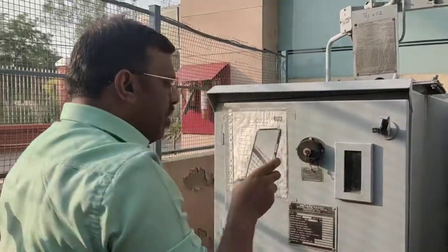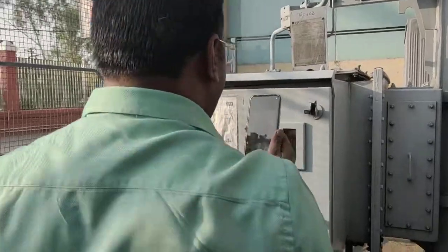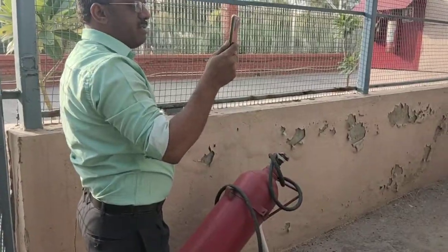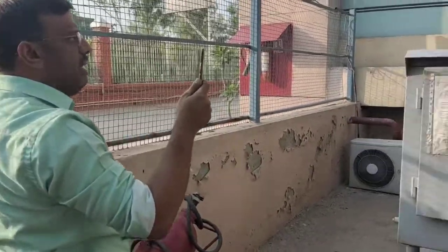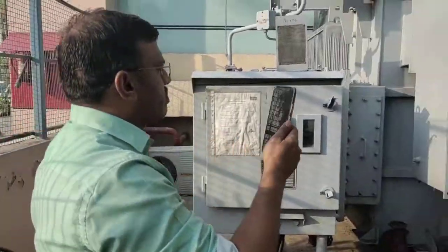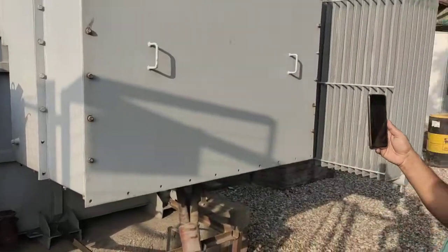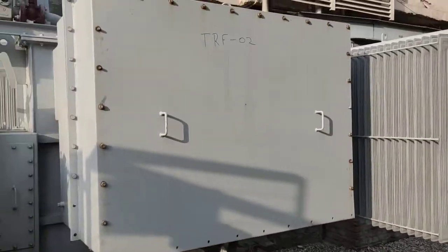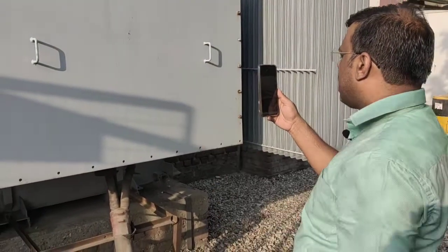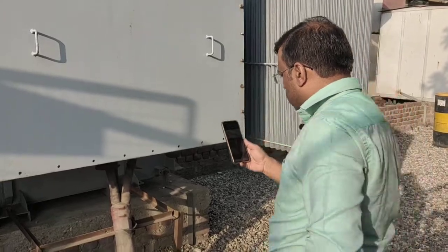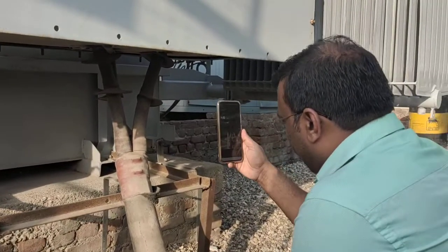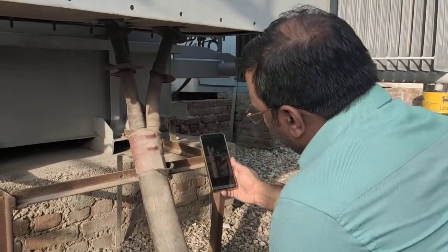Okay, so now we have discussed this 2500 kVA transformer, how it looked. We have already discussed earlier also, but we have not discussed what the basic fundamentals show. So now this is your HT side, this is your HT input, that is the primary winding, and just beside that is the secondary winding. Okay, so what we are talking about, the HT cable, this is the XLPE HT cable of 300 square mm.